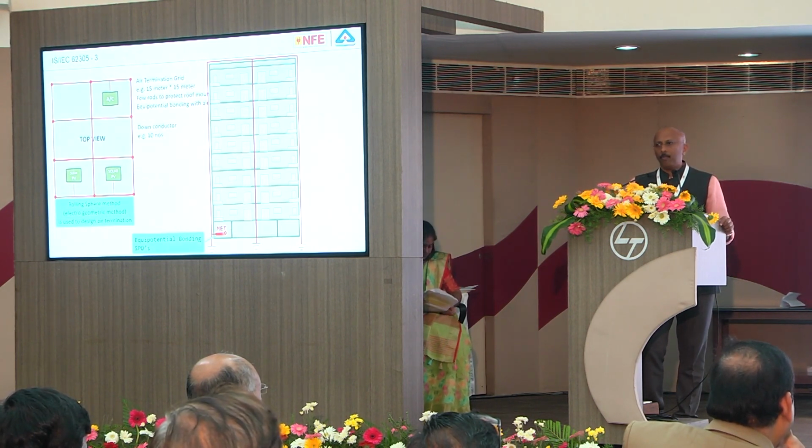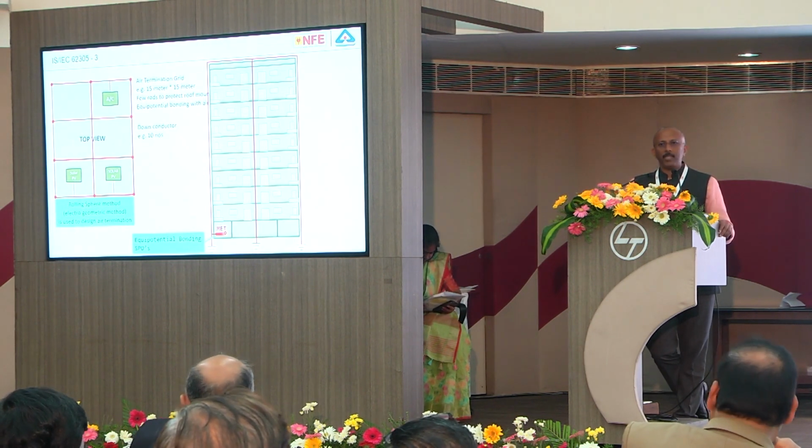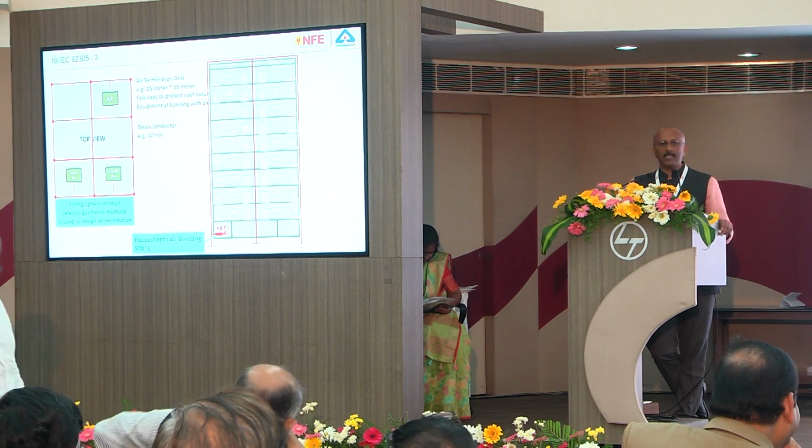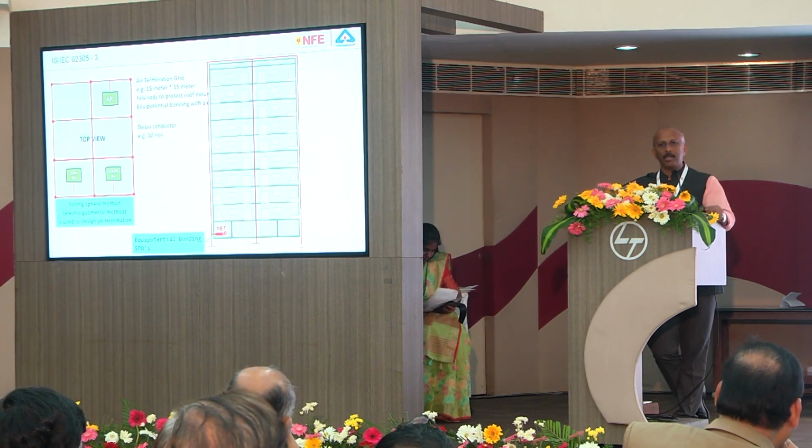One of the problems, once when we go to inspect a lightning protection system, in 99% of the installations, is this kind of equipotential bonding, that means the down conductor bonded to the earth bus bar: is it existing or not?